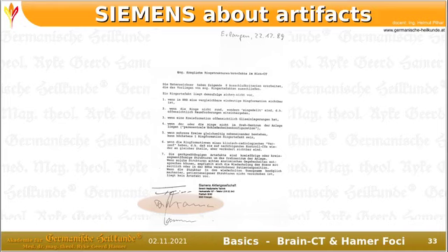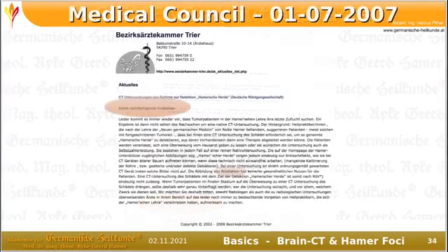We can also repeat the shot and move the patient by 2 inches. The real Hamer focus, of course, must move along with the patient. The artifact always remains in the pivot of the machine. So, there are very simple exclusion criteria. You can find this document on the internet or in the literature, in Dr. Hamer's books. I just want to say, who can judge this better than the manufacturer himself, what this should represent?